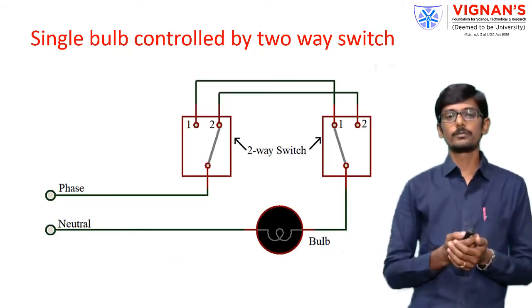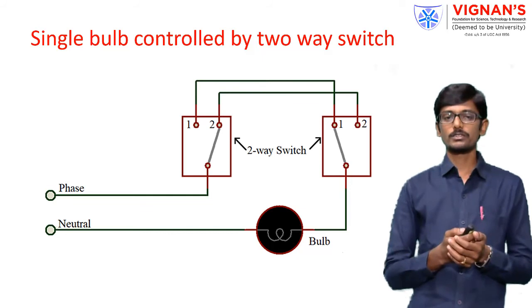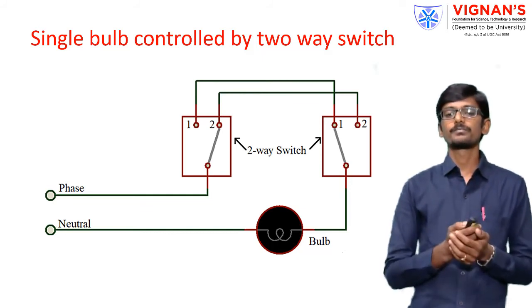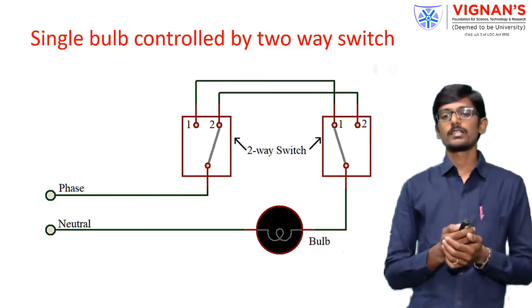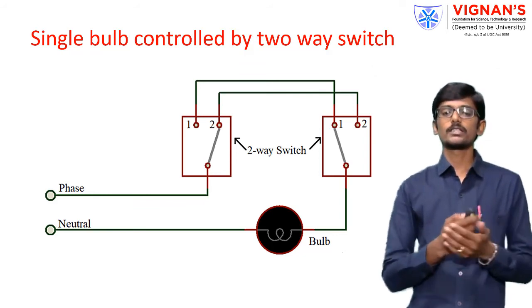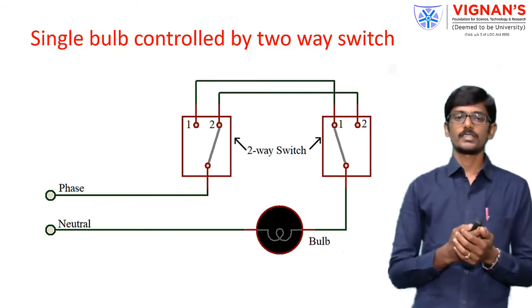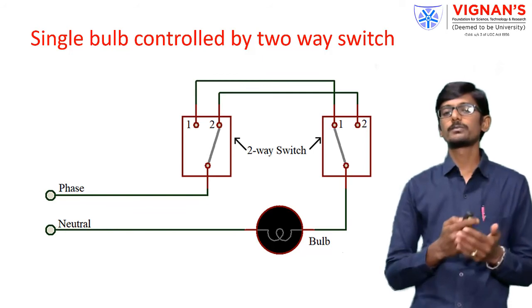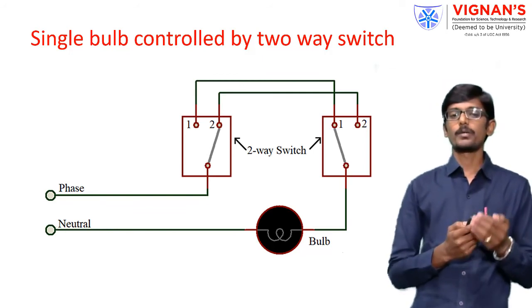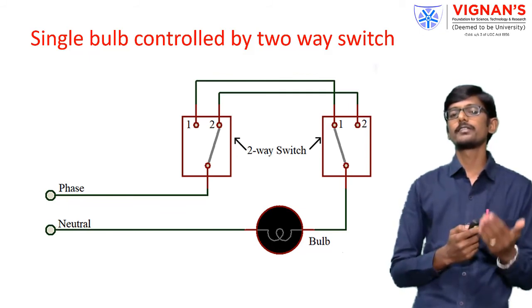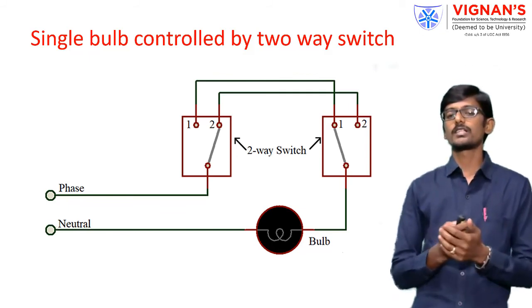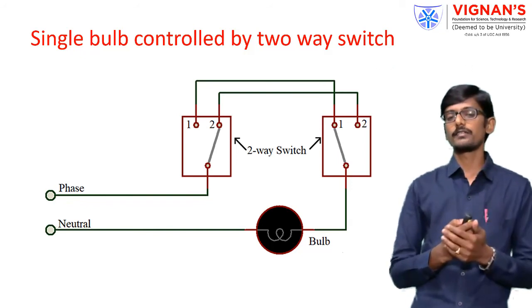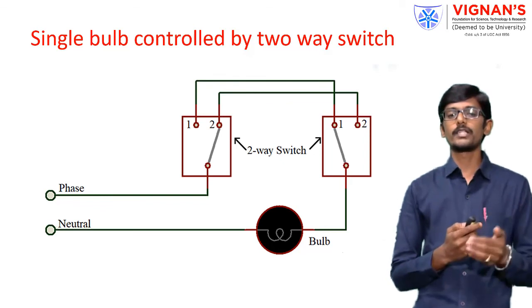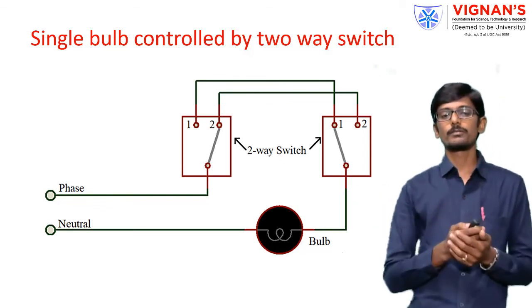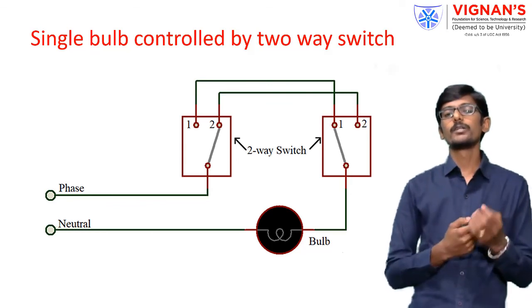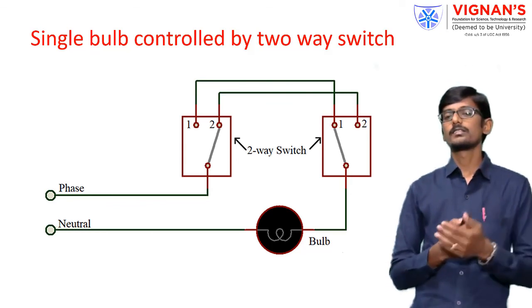Here, the single bulb is controlled by two-way switches. The connection circuit shows that the first switch is connected to the second switch, and the neutral is connected to the bulb. Here we have a single bulb connected to two-way switches. Two-way switch means the switch consists of 2 points. On the input side we have 1 point, and on the output side we have 2 points. Similarly, the other two-way switch also has 1 point on the input side and 2 points on the output side. So, when the supply flows from the phase, in this figure, the direction of current flows from phase to the input point, and the single bulb will be controlled by two-way switches. This is the circuit example.